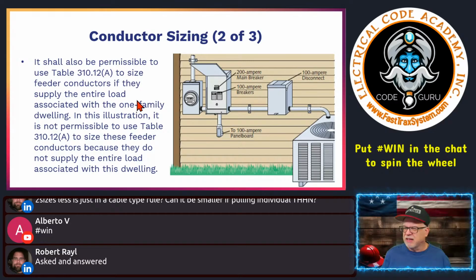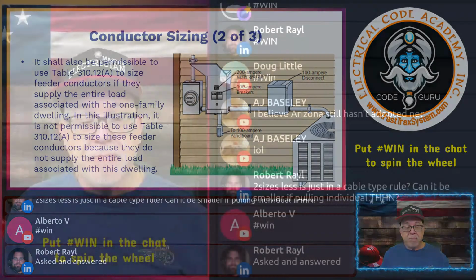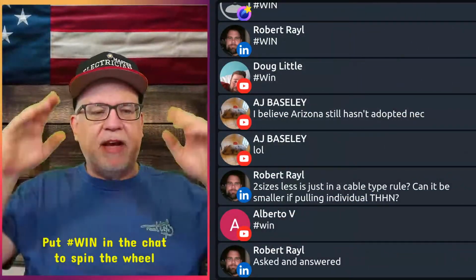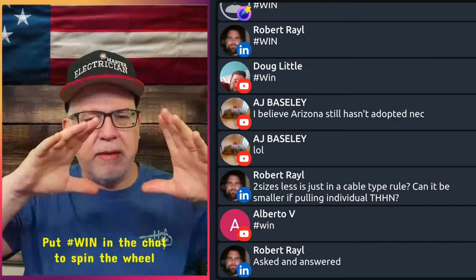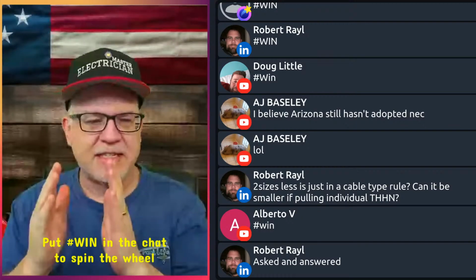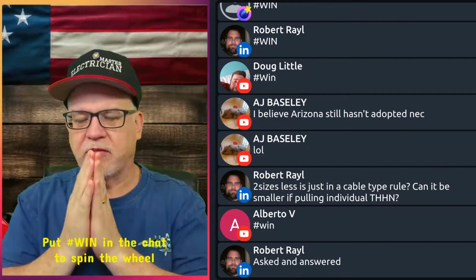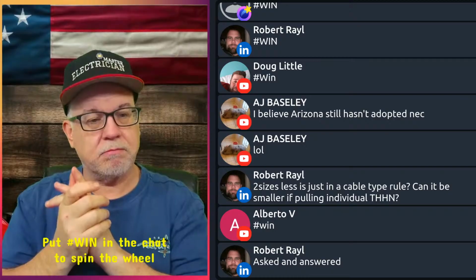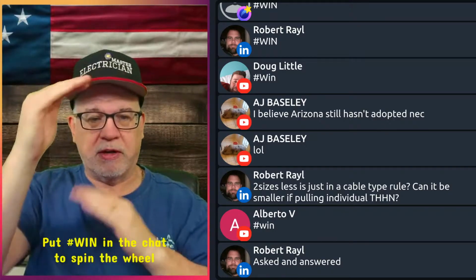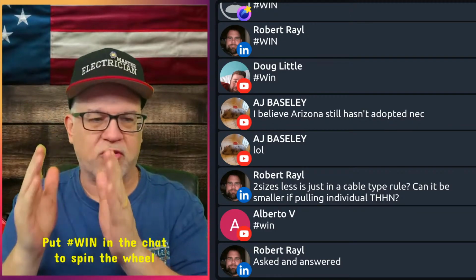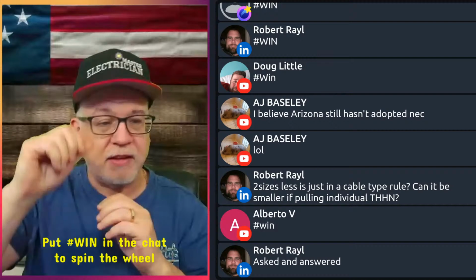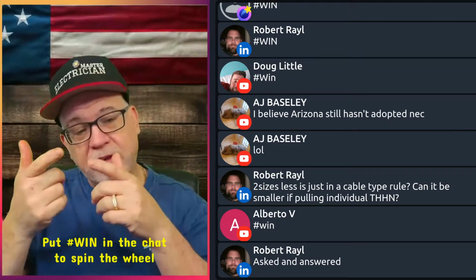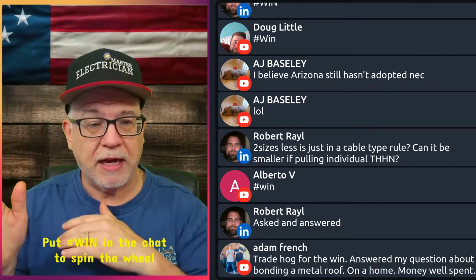Not for those. And again, my better example of when you can use the 83% for the feeder is if I came from the weatherhead and I came down to a meter and I came over and I hit a disconnect. And it was a service disconnect. It's kind of like the 200 amp ones, the NEMA 3R ones. It's just a service disconnect. That's all that's in there, the main breaker. And so anything on the load side of that is a feeder, right?